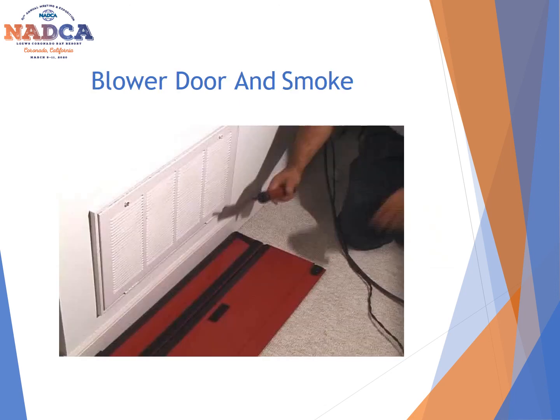If your HVAC system is tight and there is no duct leakage, when you put on a blower door, you should not be getting any air in or around the registers themselves. So even going to the return with the unit turned off, you should be able to hold smoke up to it, and if you see air being pulled in or if you see air being blown around the register, then you know that the register itself needs to be sealed.